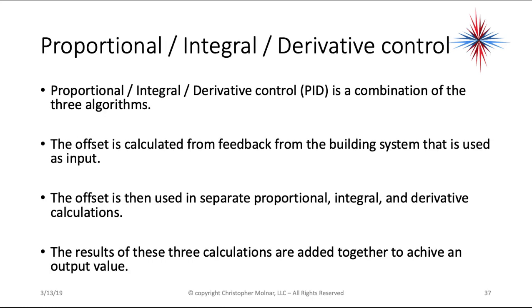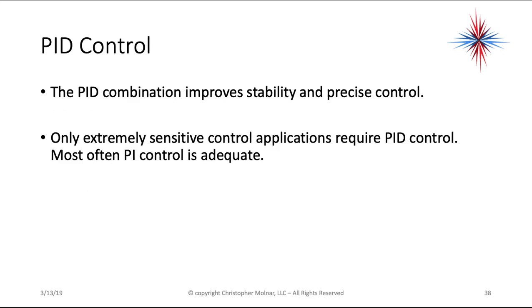The solution is PID control — a combination of proportional, integral, and derivative algorithms. The offset is calculated from feedback from the building system and used as an input. The offset is then used in separate proportional, integral, and derivative calculations, and the results are added together to achieve an output value. PID improves stability and gives more precise control. Only extremely sensitive control applications require PID; most often, PI control is adequate.